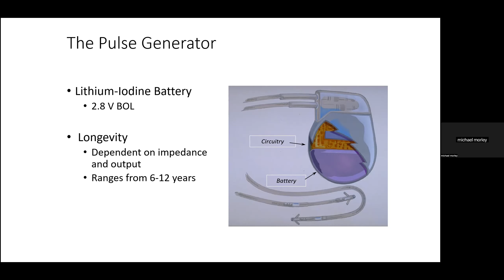And the reason that pacemakers can last so long is that the current drain for each impulse is tiny, because the resistance of the leads is so high, and because the impulses are of such short duration. So typically the impulse will be 0.4 milliseconds, which means that you're only getting about 30 seconds of current drain a day, or about 3.5 hours of current flow per year. And in the life of the device, you may only have 30 to 40 hours worth of actual current flow. And that's the reason that pacemakers can last for such a long time.